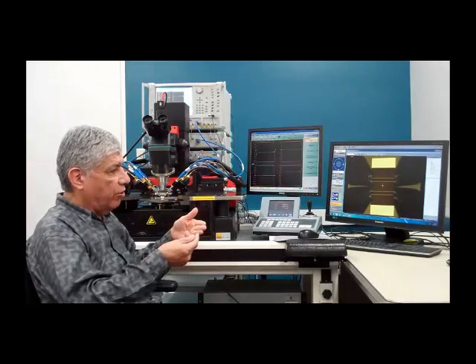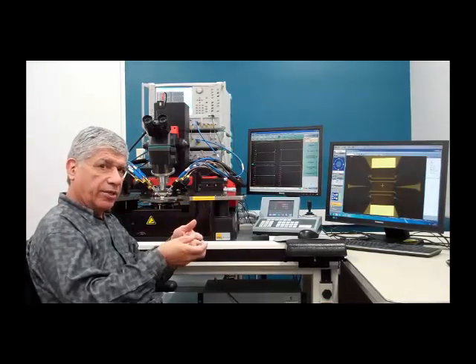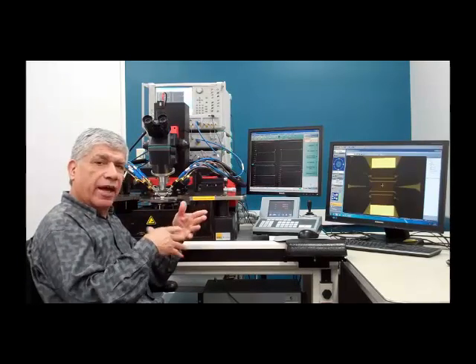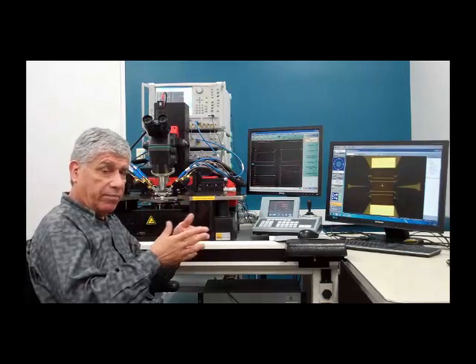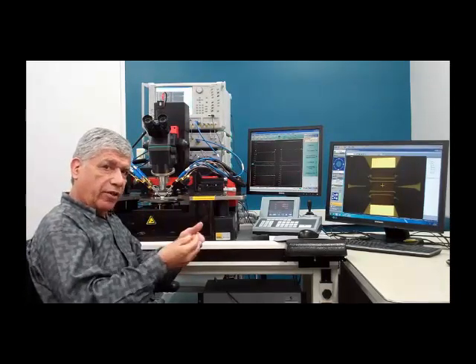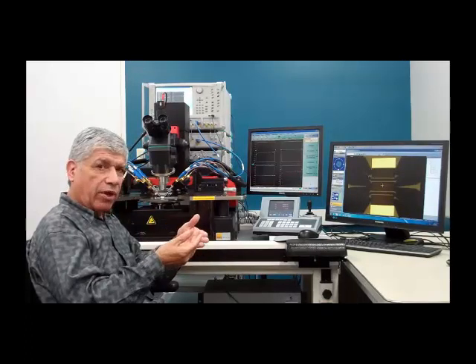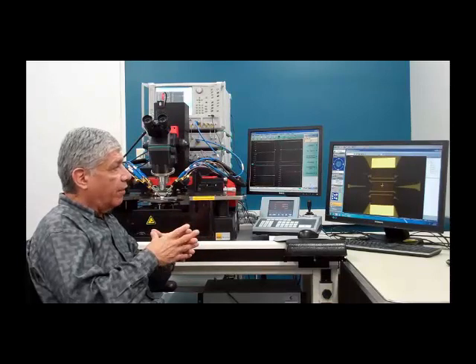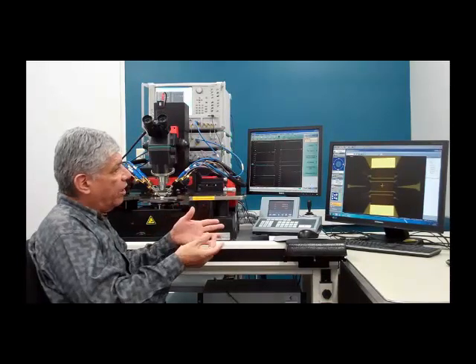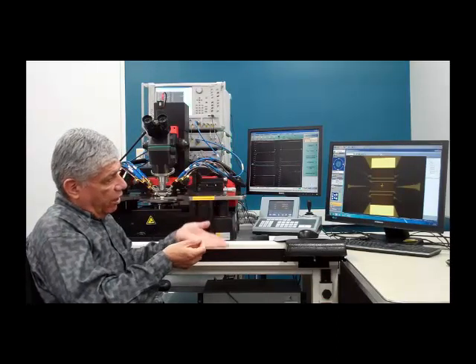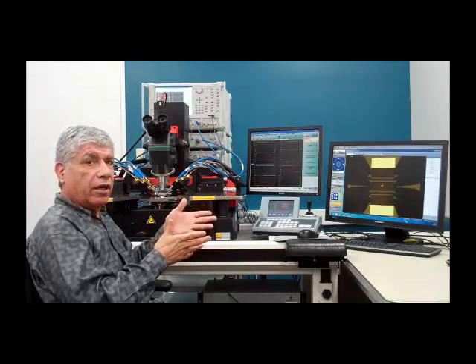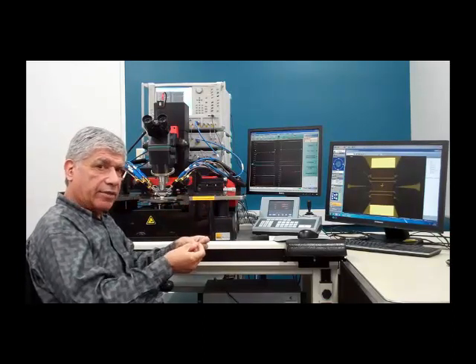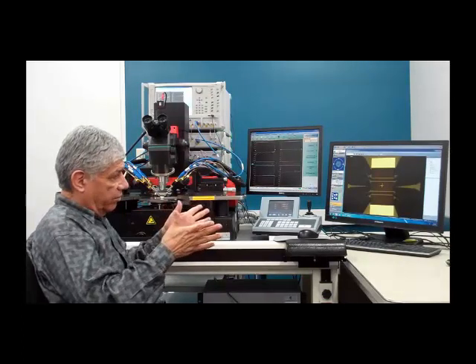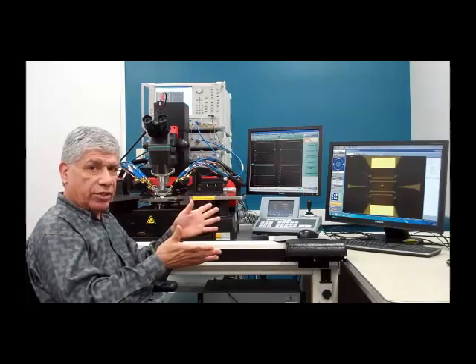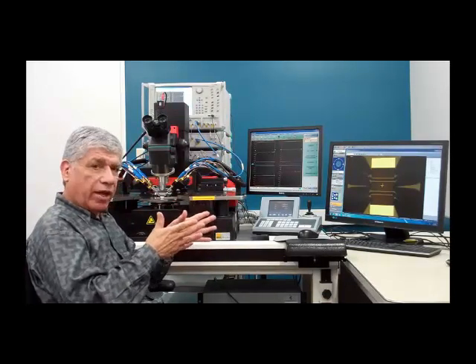Now, of course, this is the Cal standard, and what we would want to do is go to a different through in order to do the true evaluation of the calibration. The next thing we would also do, if we want to start looking at stability of the system, is go to a different through, store that into memory, do a data divided by memory, and look at it over a period of time, and that would give you a good stability. Another thing you could be doing at this point is doing a number of touchdowns in order to see what the repeatability of your probes and contact on pads are. So that's concluding basically the calibration and setting it up, getting ready for our DUT measurements.